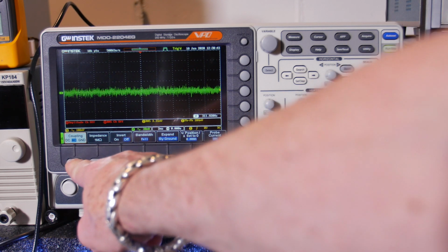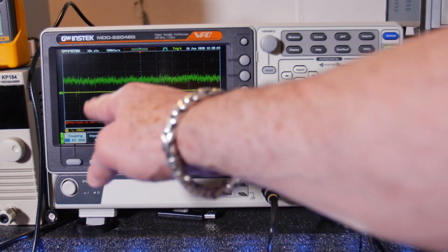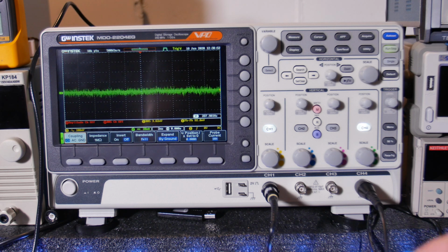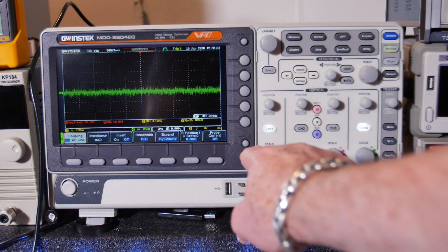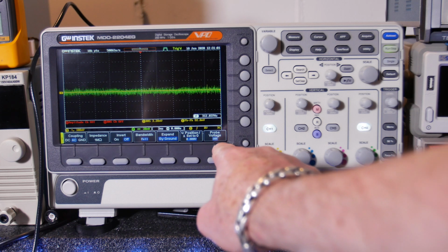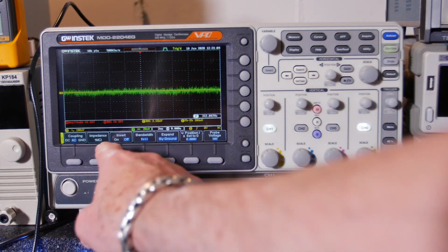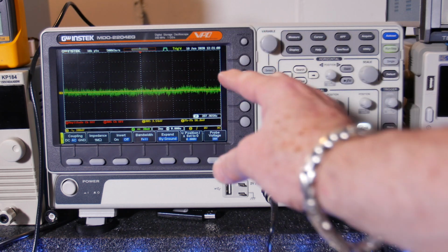Great. And you know what? Let's go ahead and just AC couple it. Well, I want to DC couple just to make sure that I have it. See how it's offset right now? I just want to make sure I have it degaussed. So when there we go. Now it's degaussed. It's in the center of the screen. So, okay. Full bandwidth, all that stuff. We haven't changed anything there. So let's go channel 1 ×10 as well.